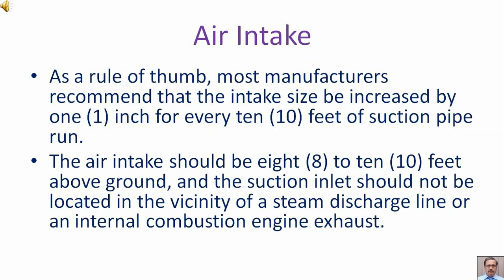As a rule of thumb, most manufacturers recommend that the intake pipe size be increased by 1 inch for every 10 feet of suction pipe run. The air intake should be 8 to 10 feet above ground, and the suction inlet should not be located in the vicinity of a steam discharge line or an internal combustion engine exhaust.